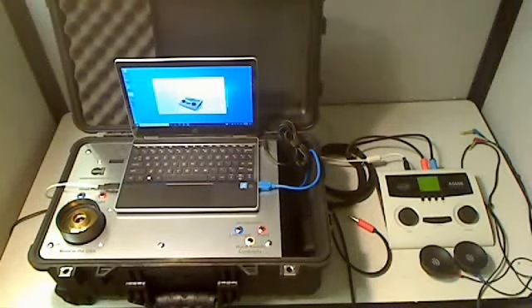What you're looking at is me setting up to calibrate an Interacoustics 608 audiometer. Now that could be a Beltone, a Tremetrics, a Monitor, a GSI, Maico, any of these interface units. They all work the same with this calibrator, which is an ACS Model 102 calibration and analysis system.